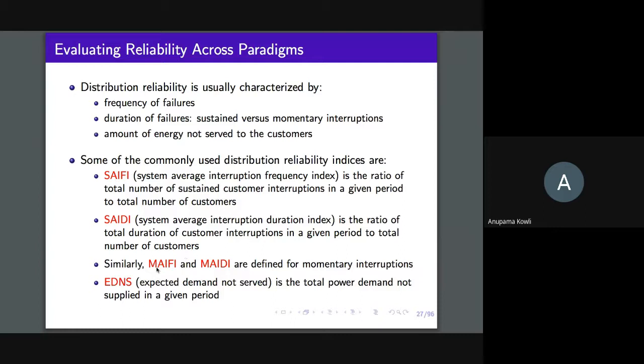MAIFI is momentary average interruption frequency index. MAIDI is momentary average interruption duration index. These are frequency and duration indices that regulators use to characterize the performance of a utility in terms of how reliable the supply is that they are able to provide.